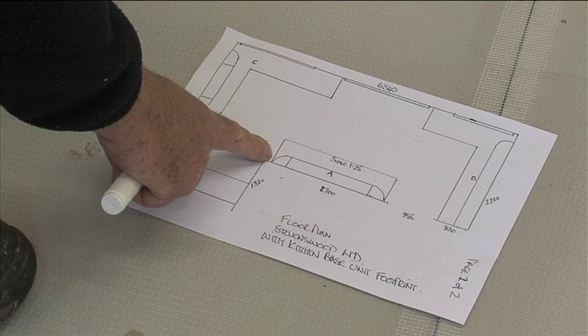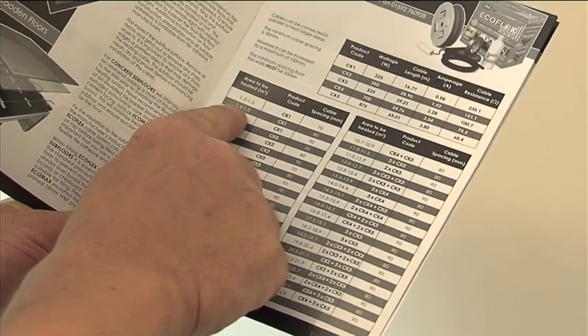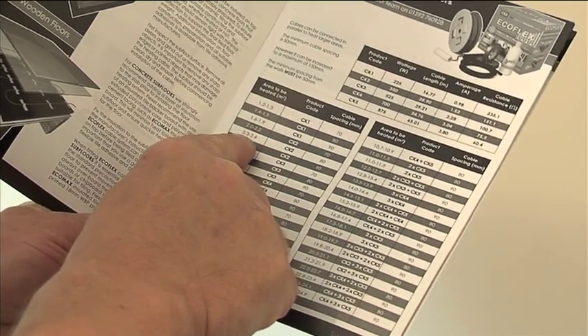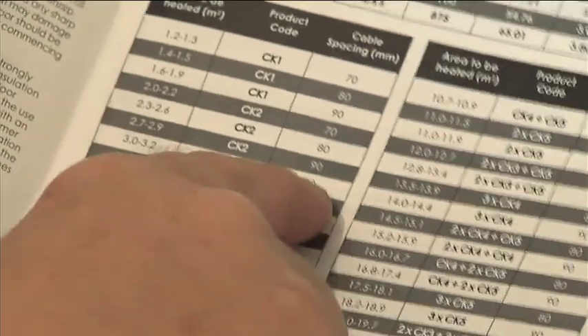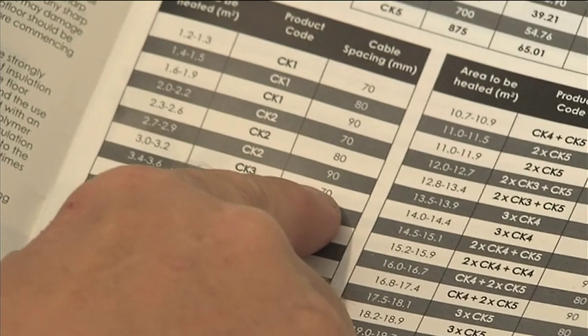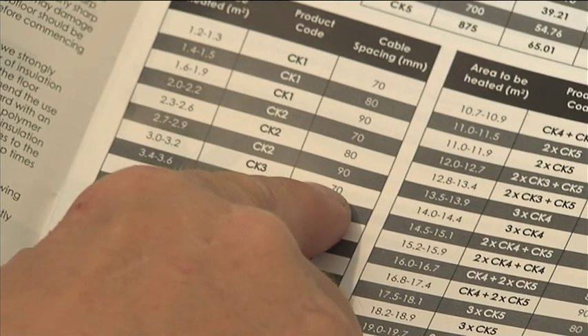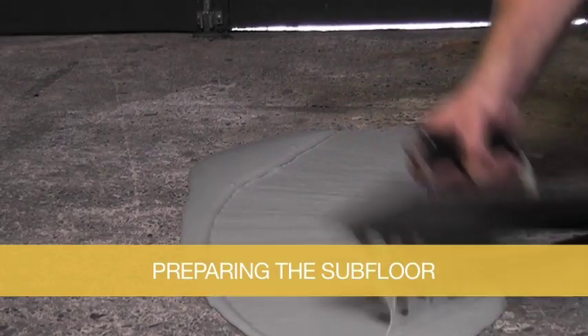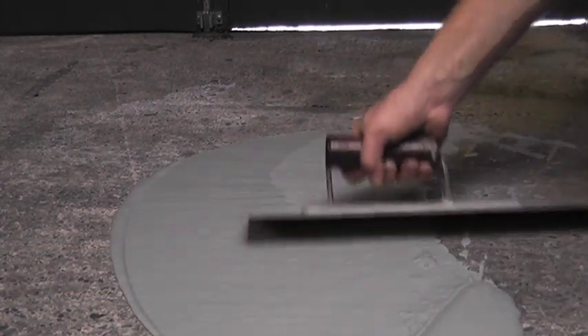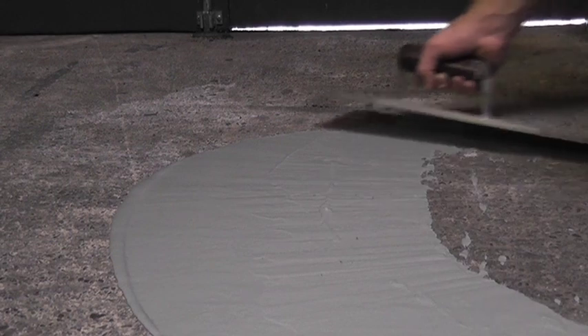We recommend that you spend time planning the installation and accurately calculate the free area of the floor that you want heated. This calculated area should then be used to select the correct cable kit size. Remember to subtract any areas covered with floor-fitted furniture. It is important to select the correct cable kit size as the cable cannot be shortened. ECOFLEX cable kits can be installed on top of existing wooden or concrete subfloors that are sound and suitably prepared.